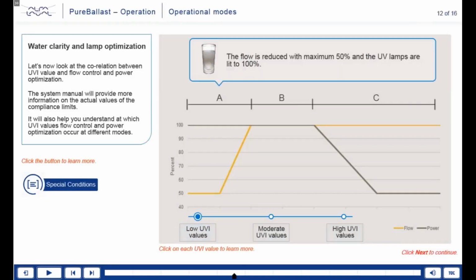In stage A, that is at low UVI values, the flow of water is reduced to maximum 50% of maximum flow, and the UV lamps are lit to 100%. In stage B, that is at moderate UVI values, the flow of water is 100% of the maximum flow, and the UV lamps are lit to 100%. In stage C, that is at high UVI values, the flow is set to be 100%, and the lamps are dimmed down to maximum 50%.